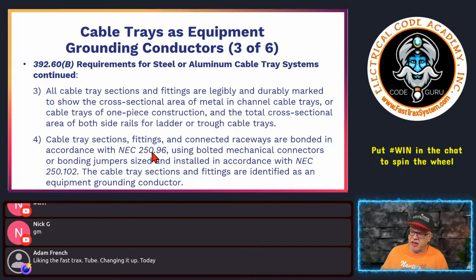Now, it also goes on to say that in order to make all these connections in 250.96, you're using bolted mechanical connectors or bonding jumpers sized and installed in accordance with 250.102. The cable tray sections and fittings are identified as an equipment grounding conductor, and if you are connecting sections with a provided coupler, or if the manufacturer provides you with the ability to go across a section of non-continuous cable tray, you need to make sure that you are sizing that bonding jumper properly based on 250.102, okay?